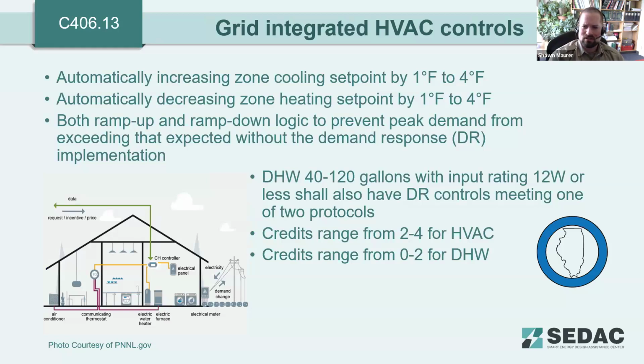Grid integrated controls, as Robert mentioned earlier, this is an Illinois amendment for HVAC systems and domestic hot water systems to have grid integrated controls. So we've put the requirements on screen here. But all thermostatic controls should be provided with a grid integrated control capable of these things: automatically increasing the zone temperature cooling set point by 1 to 4 degrees, decreasing the zone heating set point by 1 to 4 degrees, or ramp up and ramp down logic to prevent peak demand from exceeding that expected without demand response, as an alternative to the thermostat specific set point changes.